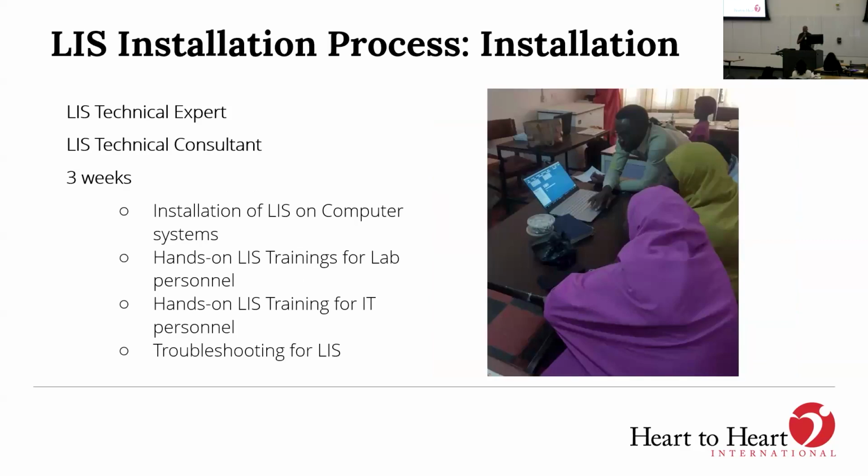Installation is about 3 weeks. We do have technologists that are trained in the software that live in those countries. Like in this particular case, one of the gentlemen that installed was from Nigeria. He's done it for several years in many, many other countries. We add additional staff if we need to, based on the workload. There are about 3 of them that can go to different countries to install these. And then we do hands-on training to the staff and troubleshooting training as well.